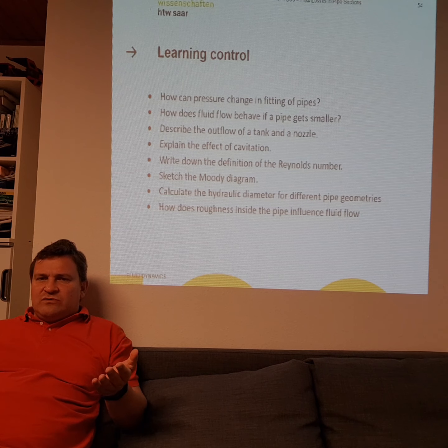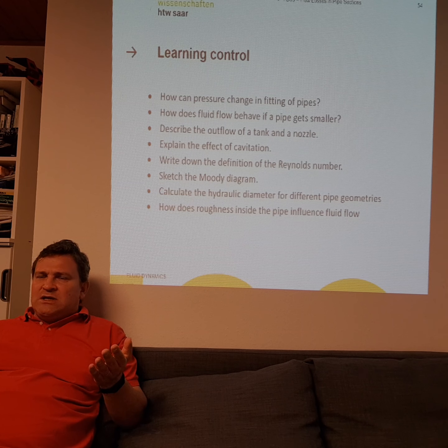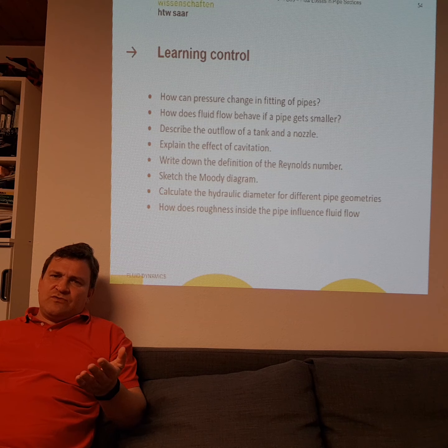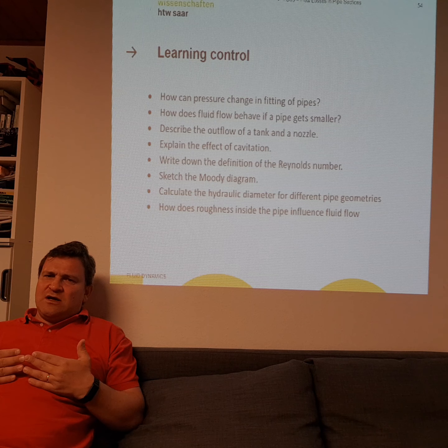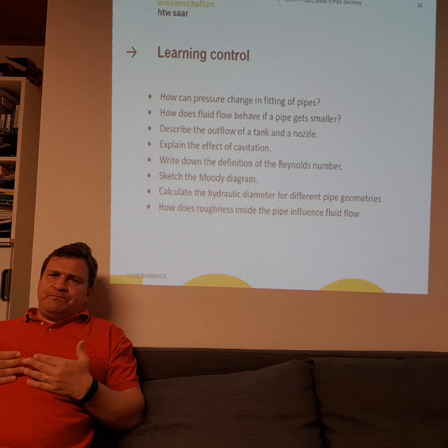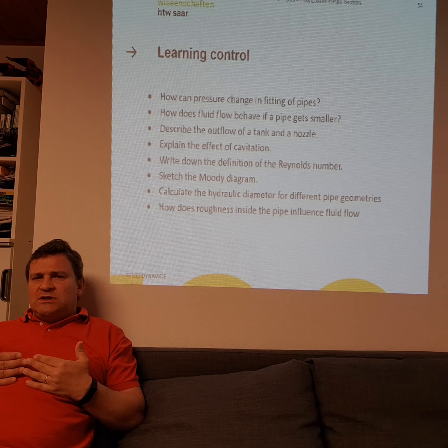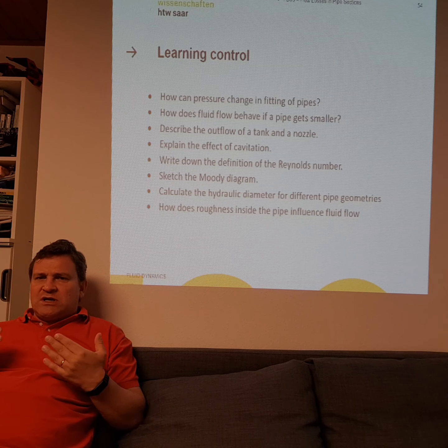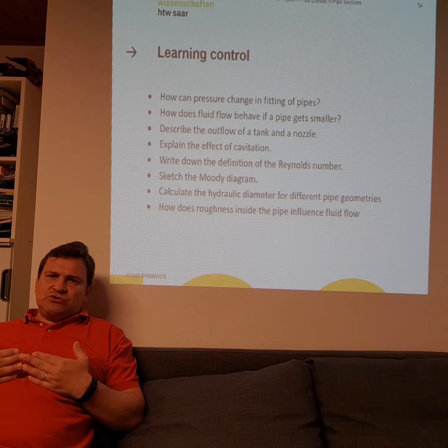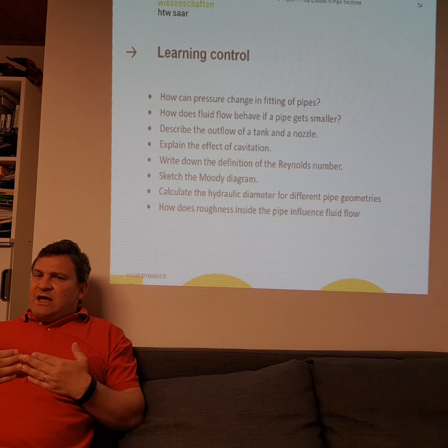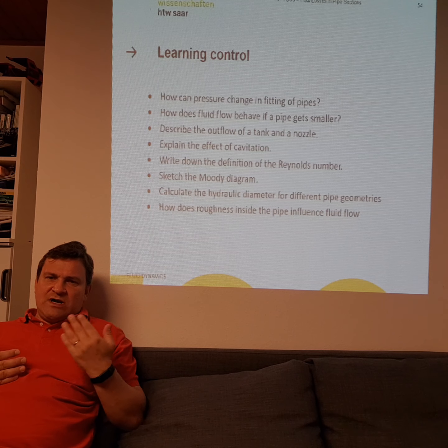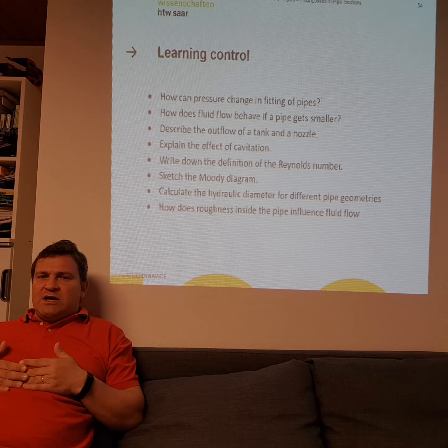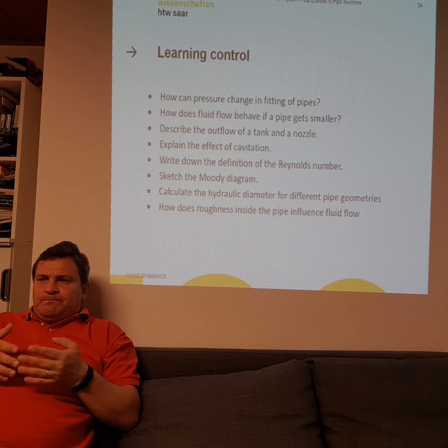You can have rectangular pipe systems for gas flows, but you will nearly never have rectangular pipe systems for liquid flows because of cavitation and erosion problems. But you must be able to calculate the hydraulic diameter, and it's always 4 times the area of the rectangle divided by the perimeter.